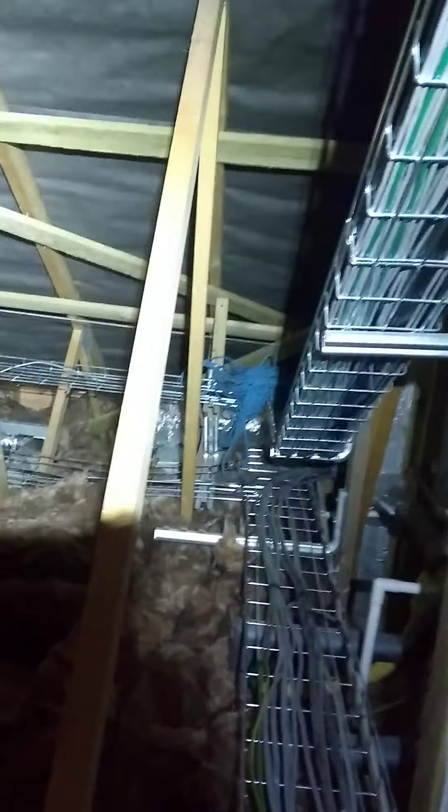These are our heating control cables coming up and popping into the heating panel at the top. There's all the plumbers' back-of-pipe work, all insulated. We had a real challenge getting cables in and out of this place, so we actually erected a catenary wire. You'll probably just about see a coil of blue nylon rope over in the corner — we put up this catenary wire system and used that with a rope attached to pull all our cables in.